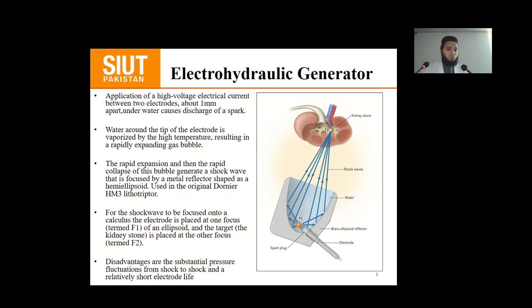We can see in the picture that F1 is the point at the ellipsoid where the shock waves are generated, and they are reflected and focused at F2, which is the point at the stone in the kidney. For the shock waves to be focused onto a calculus, the electrode is placed at one focus, termed F1, of an ellipsoid, and the target, the kidney stone, is placed at the other focus, termed F2. Disadvantages are the substantial pressure fluctuations from shock to shock and a relatively short electrode life.